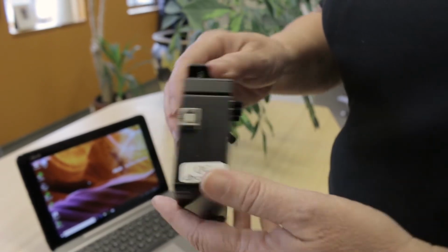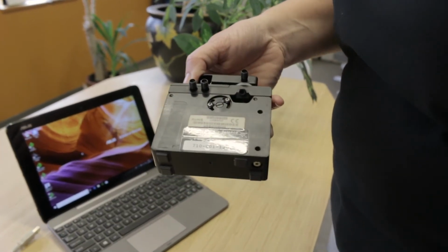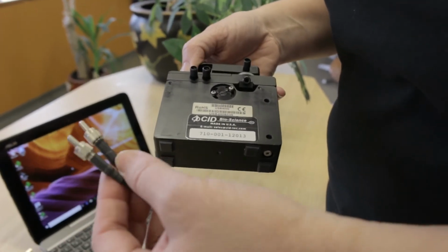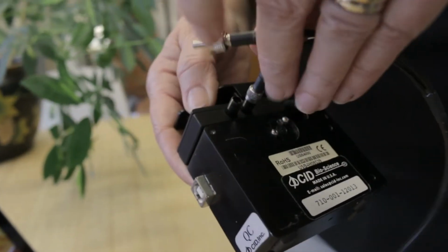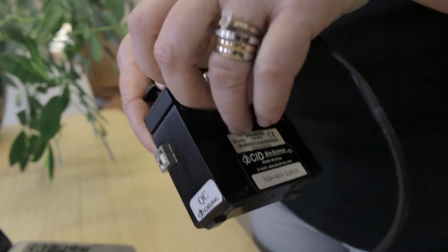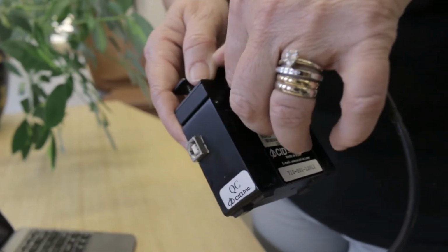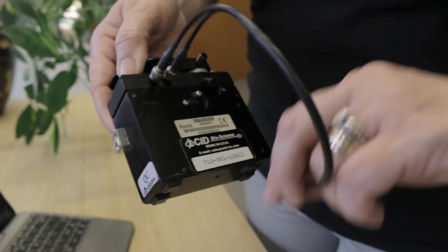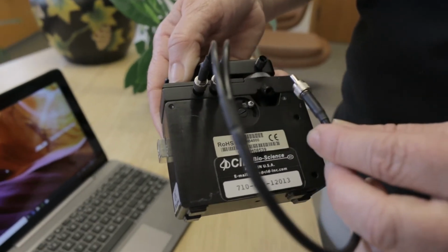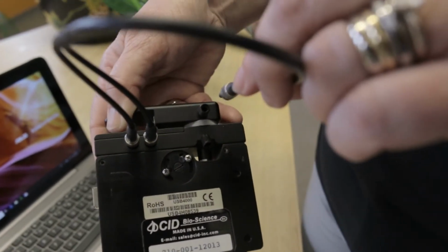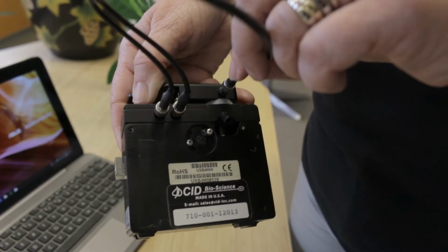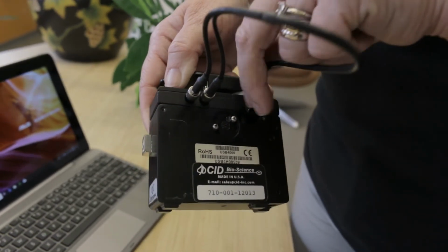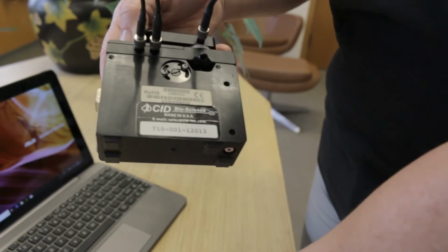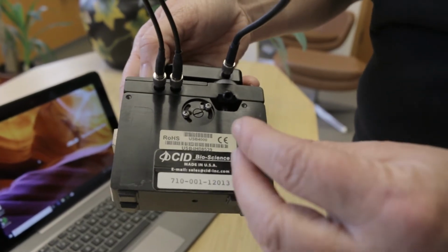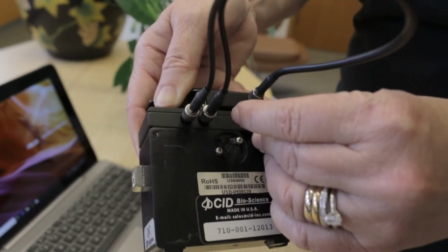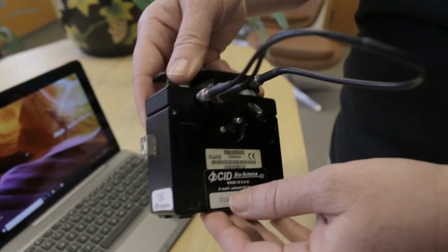To begin, attach the fiber optics cable to the device. Take the double end and insert here, twisting to secure the cable. With the other end, for reflectance mode, insert here. For transmittance or absorbance, insert here and secure the cable. Whichever port you are not using, cover with the black plastic cap to prevent stray light from entering the device.